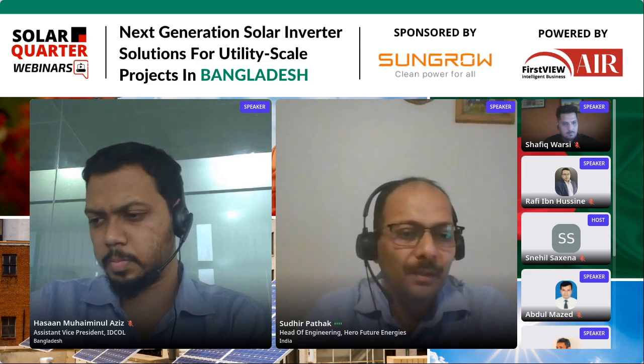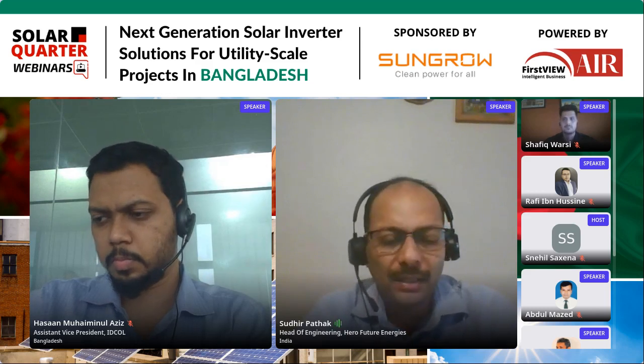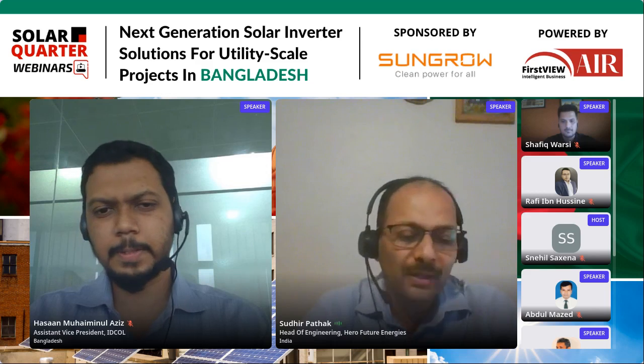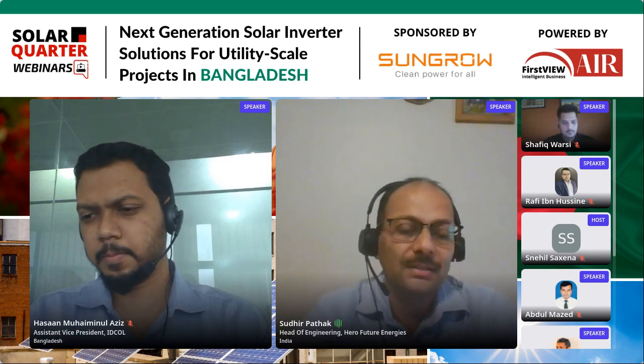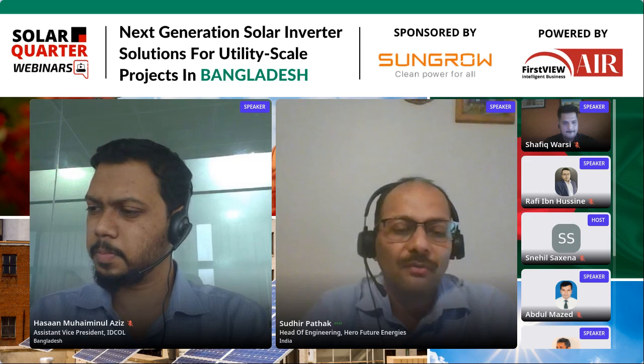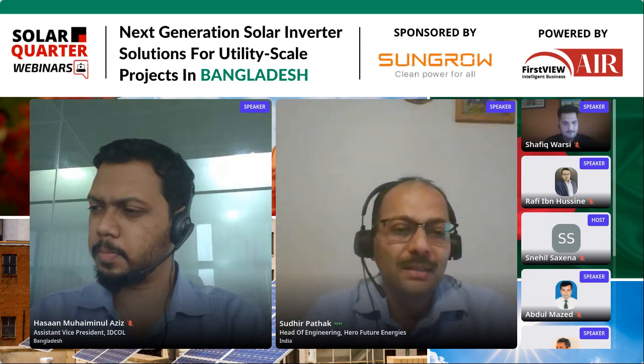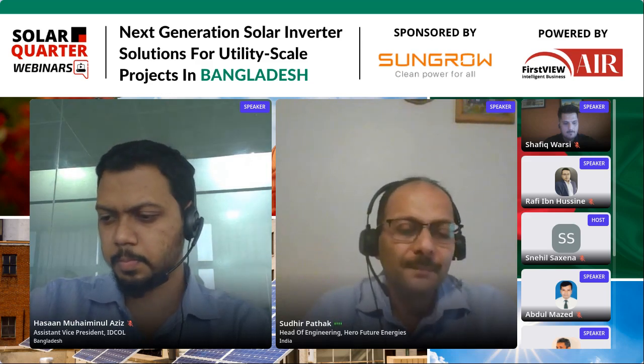So these days the efficiency of the central inverter is taken as 98.5, 98.6, which, if you take any inverter, more or less will be in the same band. But one important, or in fact two important points which we need to consider while selecting a central inverter: how many MPPTs it has, and how modular it is. In case one stack fails, is it easily replaceable?